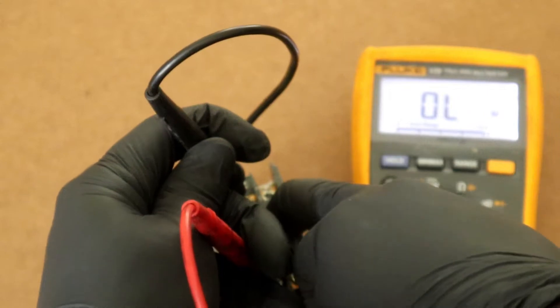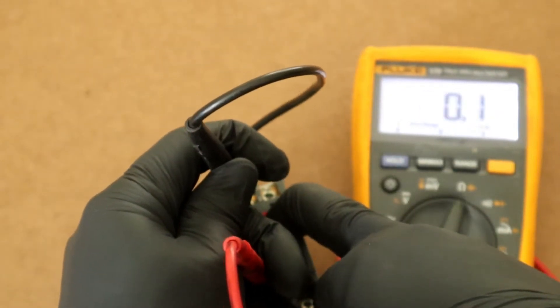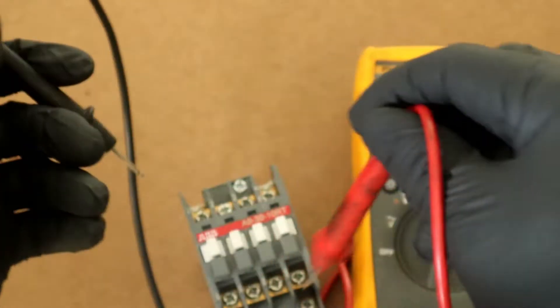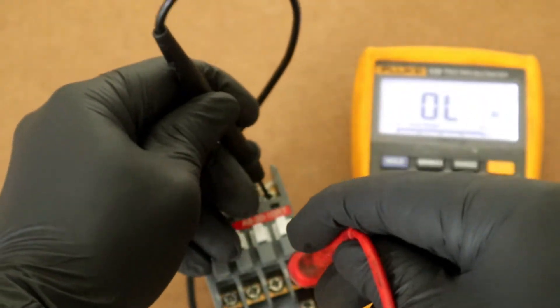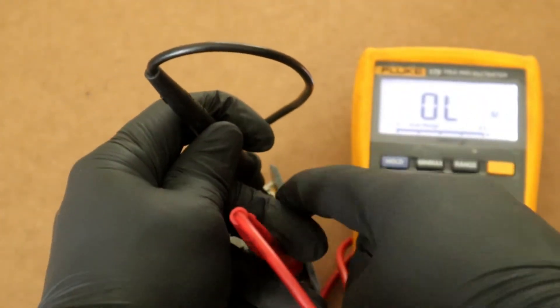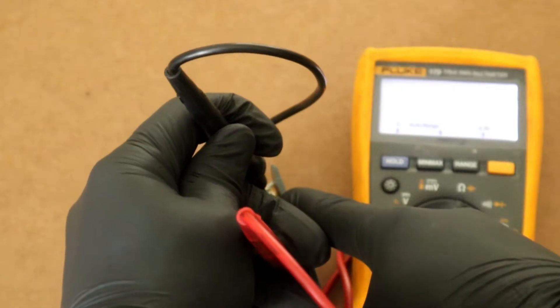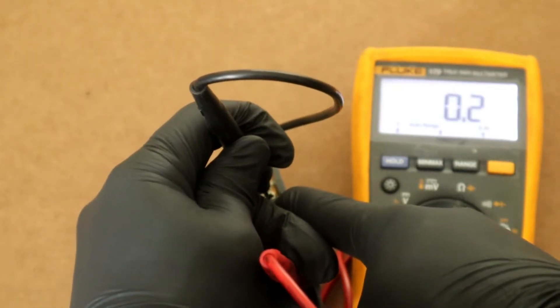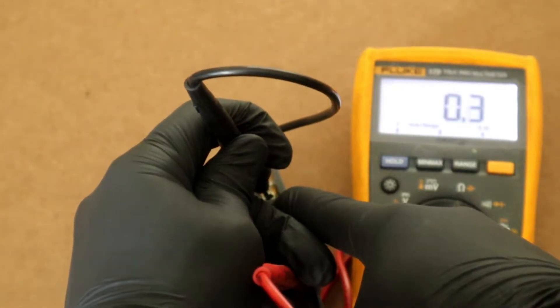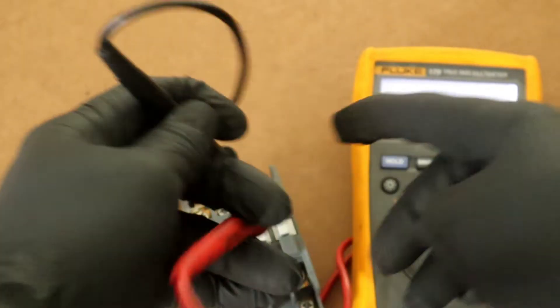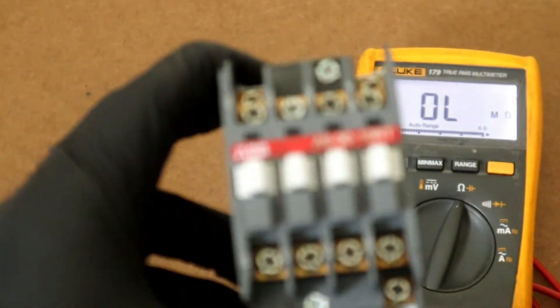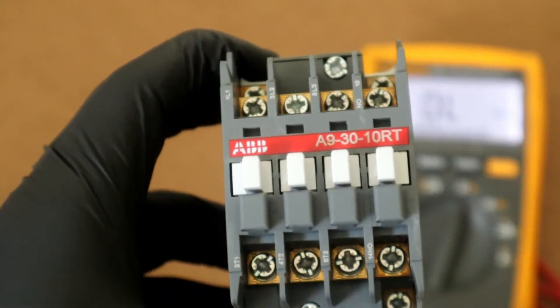L3 to T3, 0.1 ohm. So we are good so far. Now for our final contact test, we go across our normally open contact, manually depress spring, we have 0.2, 0.3 ohms. Our contactor is doing very good so far.